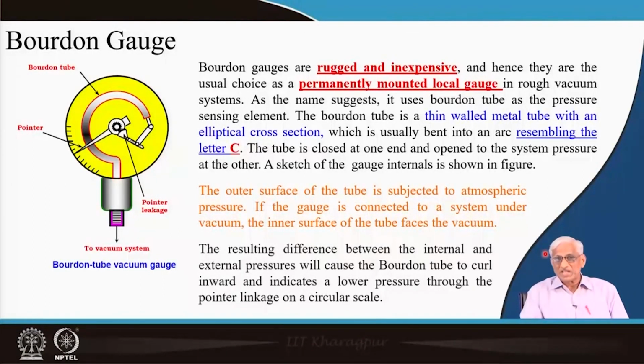You do not need to spend any extra money, and they will not get easily spoiled. Quite a good mechanically strong gauge. It is used in rough vacuum systems and permanently mounted local gauges. So maybe up to 10 millibar with a lot of accuracy you can do it. Below that it is not possible. We will see what are the limitations a little later.